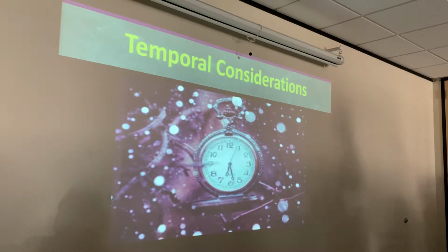Good question. Okay, let's talk about our temporal. Any other questions on spatial considerations? Remember, space, referring to distance, we're taking that beam in cross section and measuring intensity. Two ways to do that: we're going to take the spatial peak intensity, the very spot where the intensity is highest in cross section, usually the center of the beam. And we're going to take the spatial average intensity, which is usually in between, just taking a cross sectional average of those intensities across that beam.